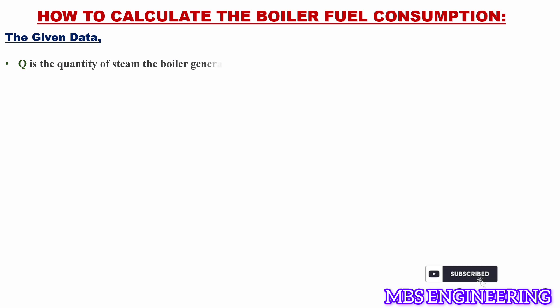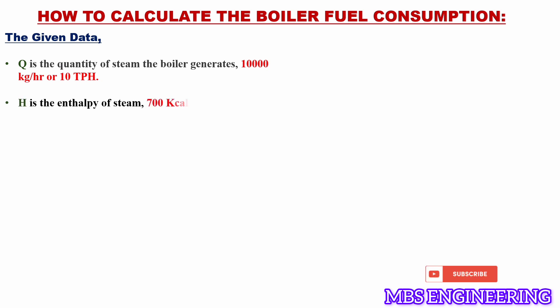We will now learn how to calculate the boiler fuel consumption. The given data is: Q, the quantity of steam the boiler generates, is 10,000 kilograms per hour or 10 tonnage per hour. Capital H, the enthalpy of steam, is 700 kilocalories per kilogram. Small h, the enthalpy of water, is 85 kilocalories per kilogram.